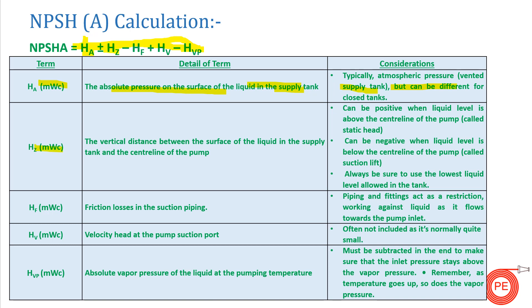The next term is plus or minus HZ. HZ is the vertical distance between the surface of the liquid in the supply tank and the centerline of the pump — in simple words, HZ is the static suction head. This static suction head is positive if the pump has positive suction, and negative if the pump has negative suction.